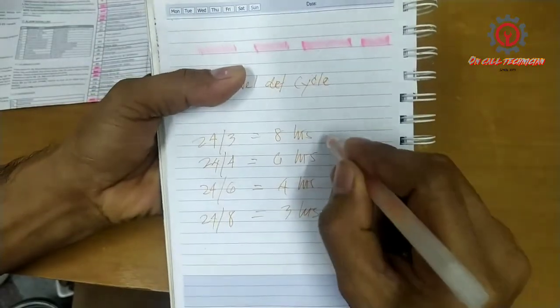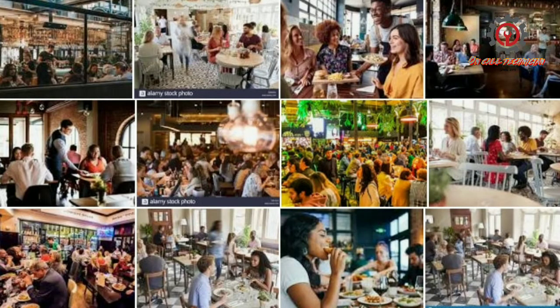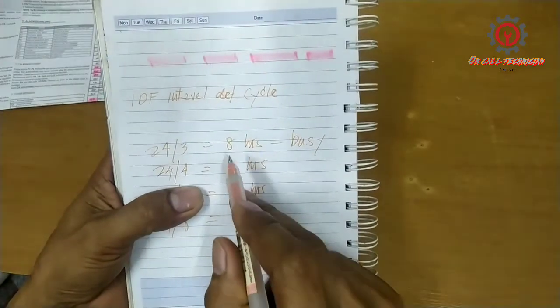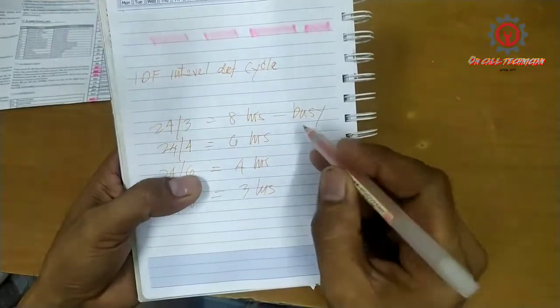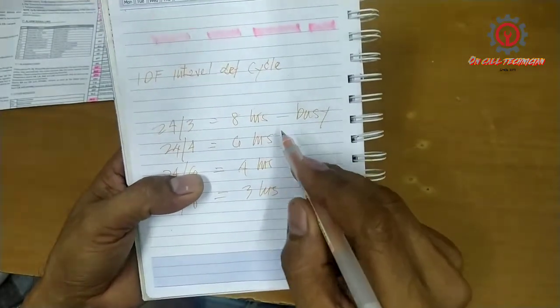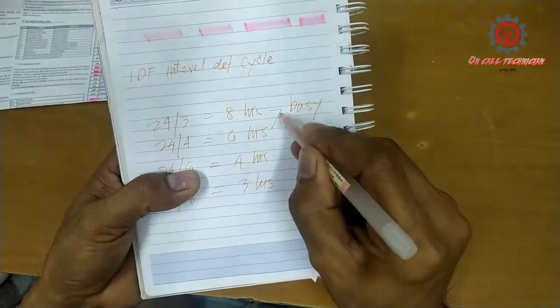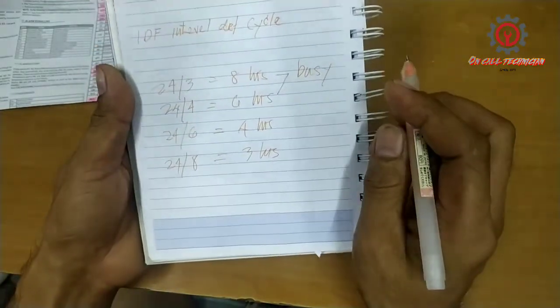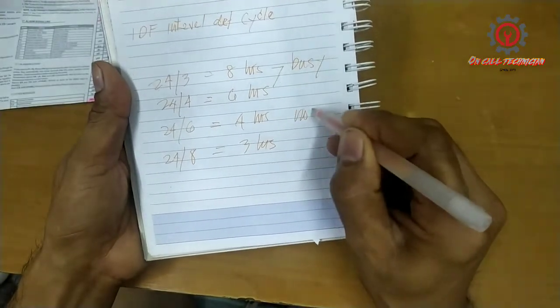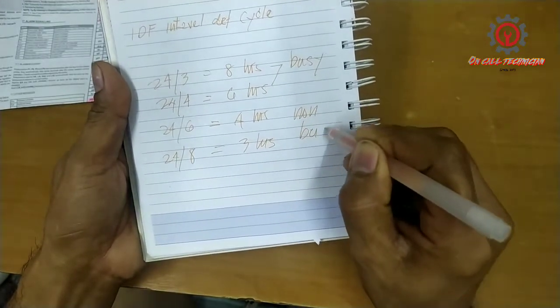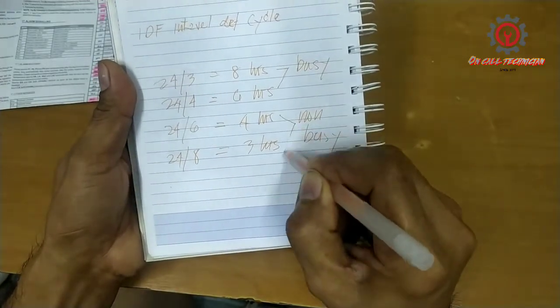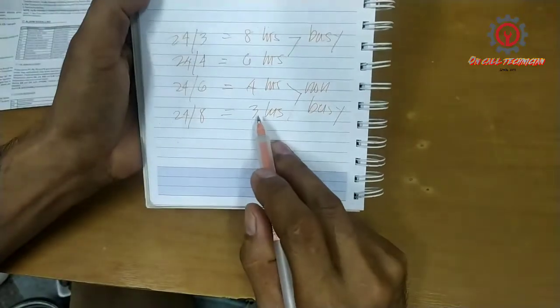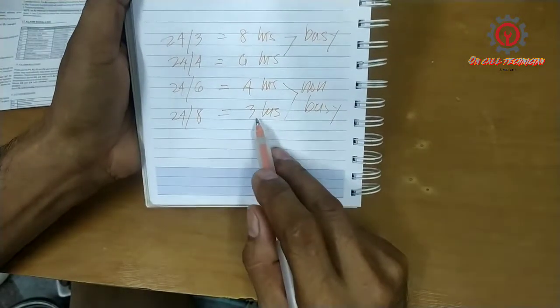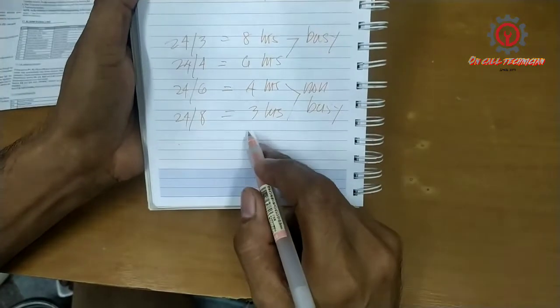Okay, this one, guys, if it is a busy restaurant or whatever, use 8 hours to 6 hours. But for non-busy, use this 4 or 3. Why? Because every time the defrost will engage, your temperature drops, and you don't want the food inside the cabinet to spoil.